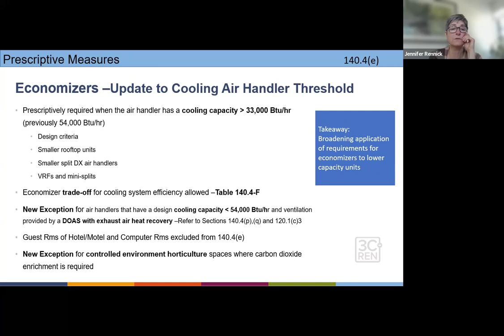And so what we're seeing is that for small commercial and residential, but the smaller commercial projects, they could have a dedicated outside air system that has small 3-inch diameter ductwork running everywhere. It doesn't have to be large ductwork to bring in the outside air. And also as a result, this entire section of the code, 140.4, has been rewritten to really address a lot of what we're seeing now with dedicated outside air systems.